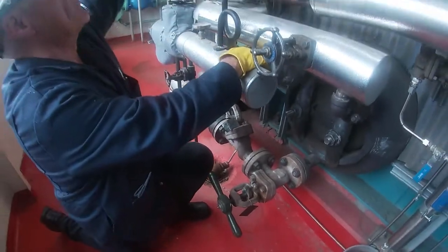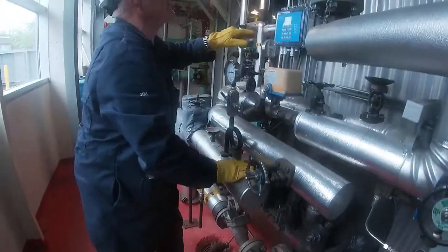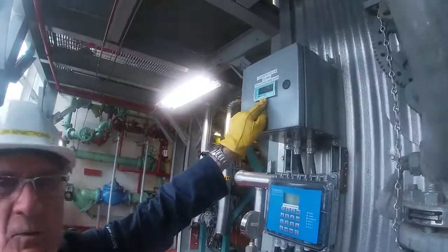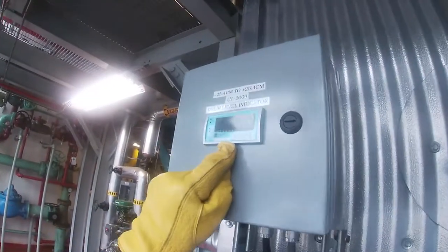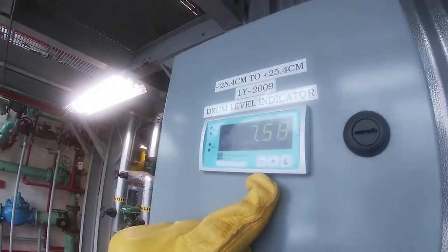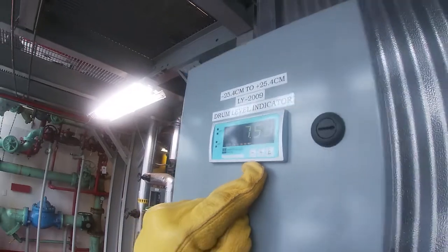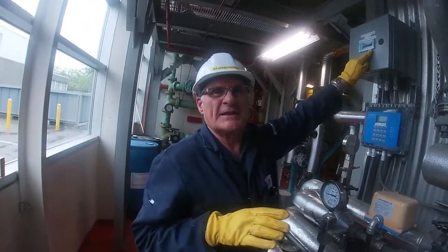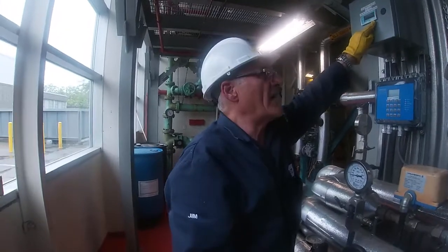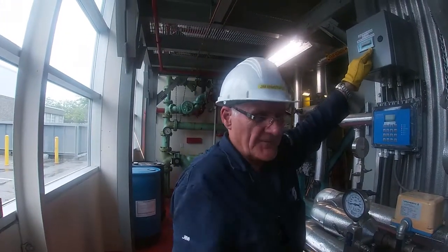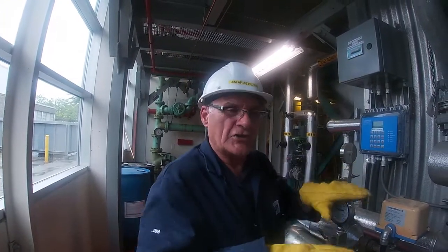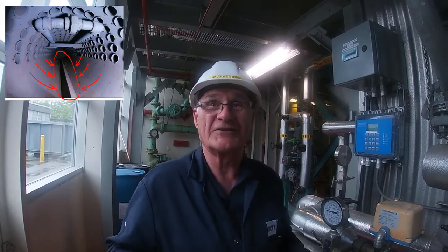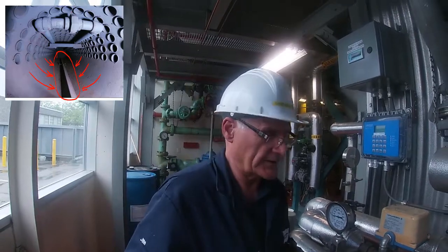And we watch the water level, which we have actually brought a remote indication of to the back of the boiler so you can see what it is. Because typically they will blow it down and you don't want to trip the boiler. This is done while the boiler is running. So I would bring this down to maybe -3 centimeters and then close those valves off. That pulls a fair amount of water out of there and gets rid of all the sludge that's accumulated in the mud drum. That's why it's called the mud drum. It's where the sludge will accumulate.